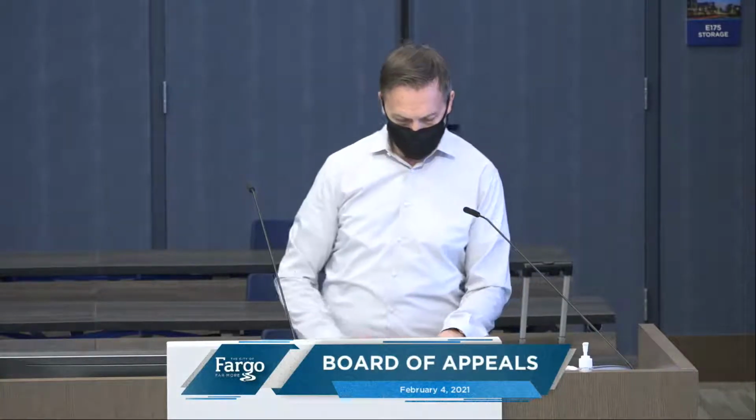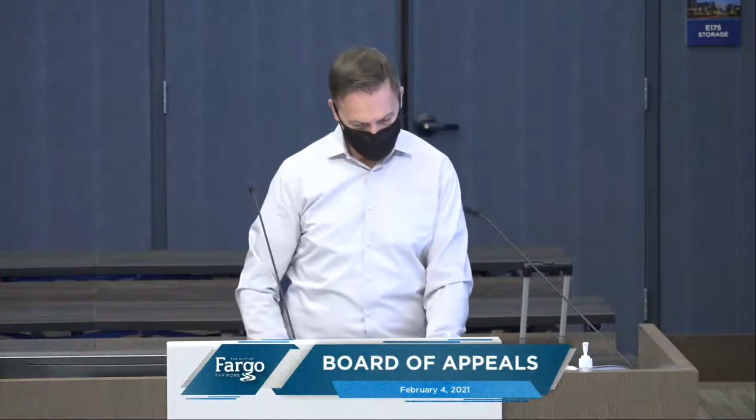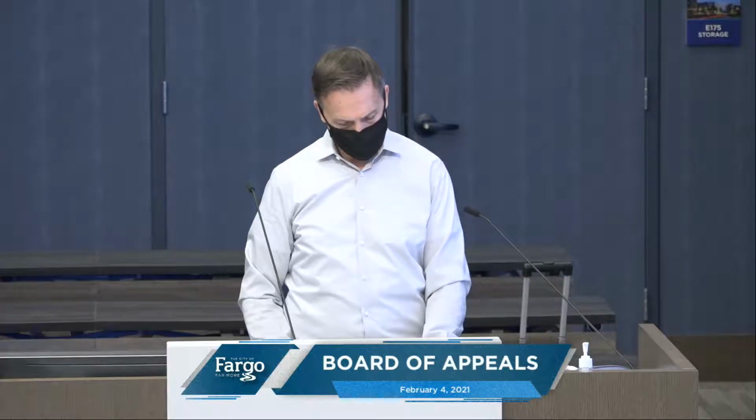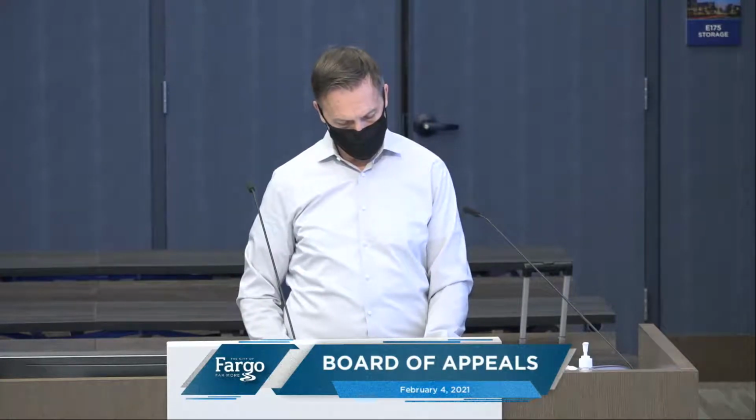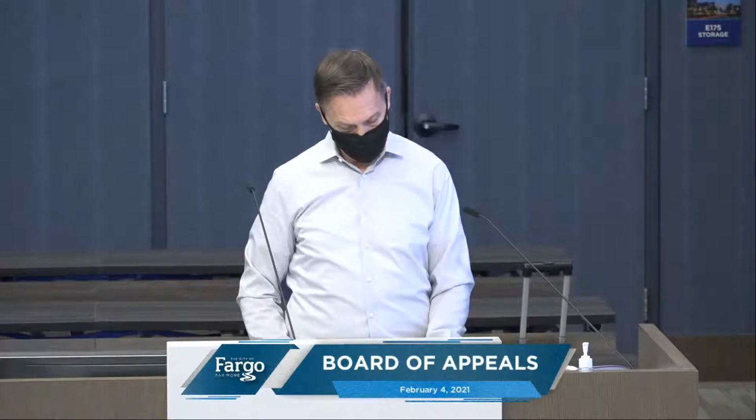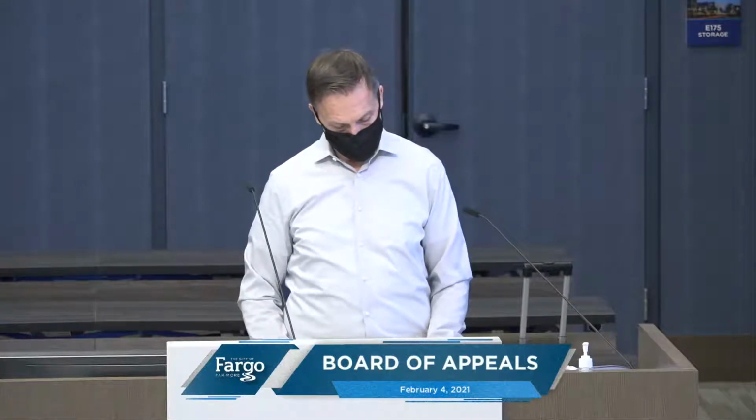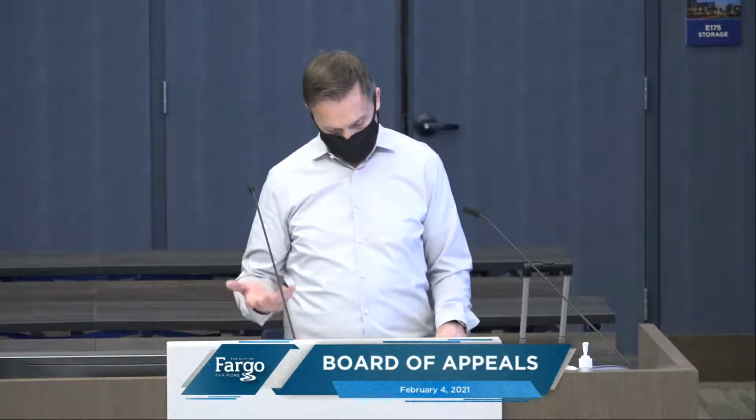It says fire barriers shall extend from the top of the foundation or floor ceiling assembly below to the underside of the floor, roof, sheathing, slab, or deck, and be securely attached thereto. Such barriers shall be continuous through concealed spaces, such as above a ceiling, and intersections complying with 707.8 and 707.9. Then we can't ignore openings. Openings in a fire barrier shall be protected, reviewing requirements of maximum amount of openings in the wall.